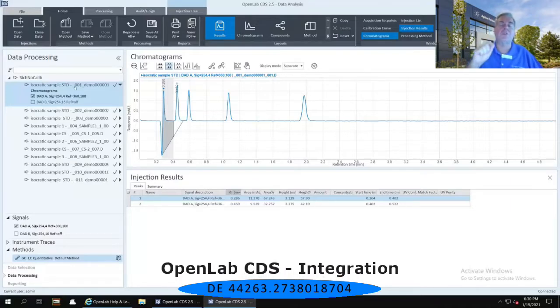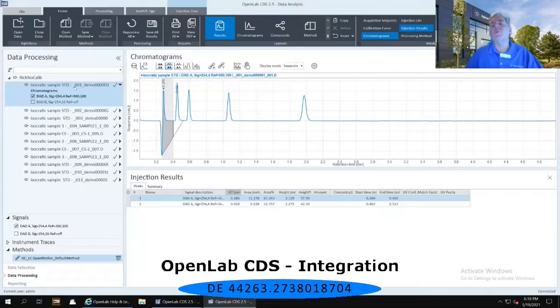I'd like to revisit my integration parameters in my method. I'm going to select the lowest concentration standard that I have — isocratic sample STD001, which is highlighted on the left-hand side. I pick the lowest because it is the most difficult for the algorithms to integrate. If it integrates this lowest level well, chances are it's going to do the other levels just fine. With this lowest level calibration standard highlighted, I'm going to go to the method layout.